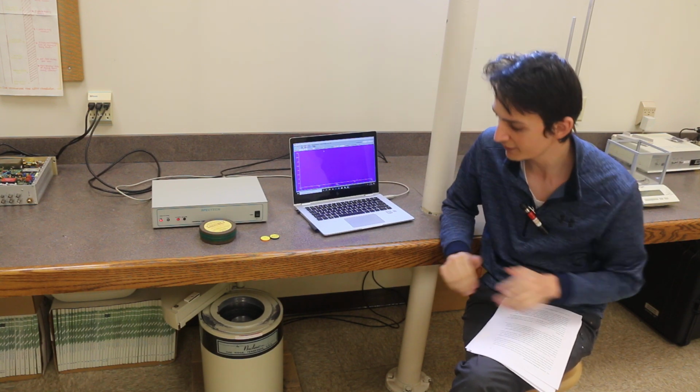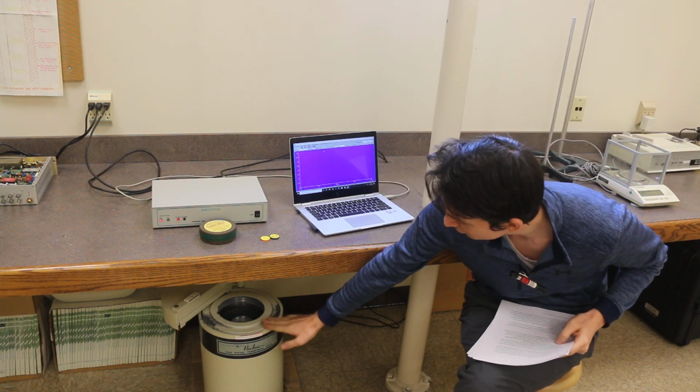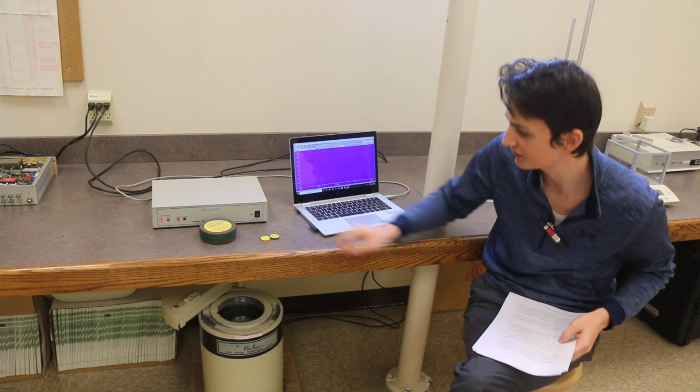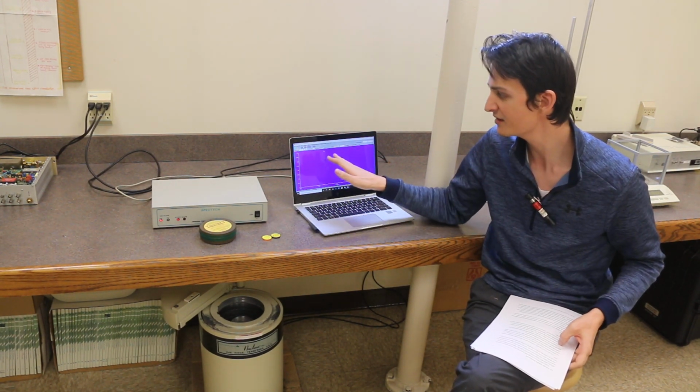Now we are using a bit different instrument than what you're used to. You're used to the tabletop scintillator crystals you have. Instead we have this big guy on the floor here as our sodium crystal. And so we have a new instrument, so we want to make sure that our settings are right, which means they're going to have to be changed.